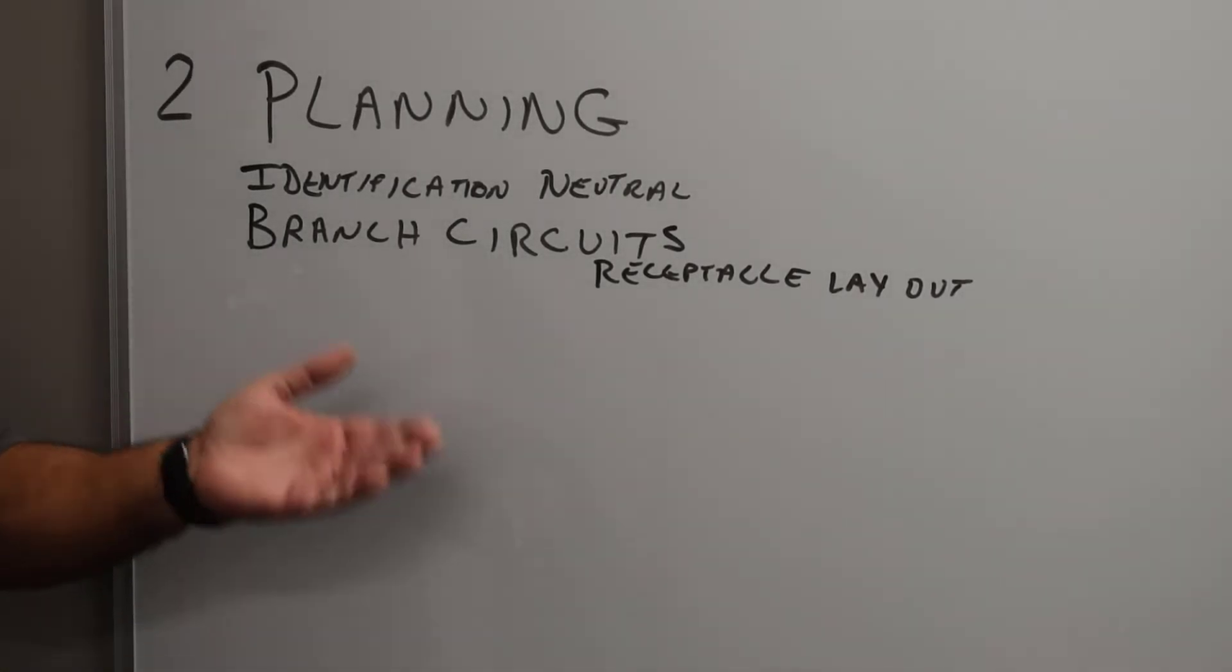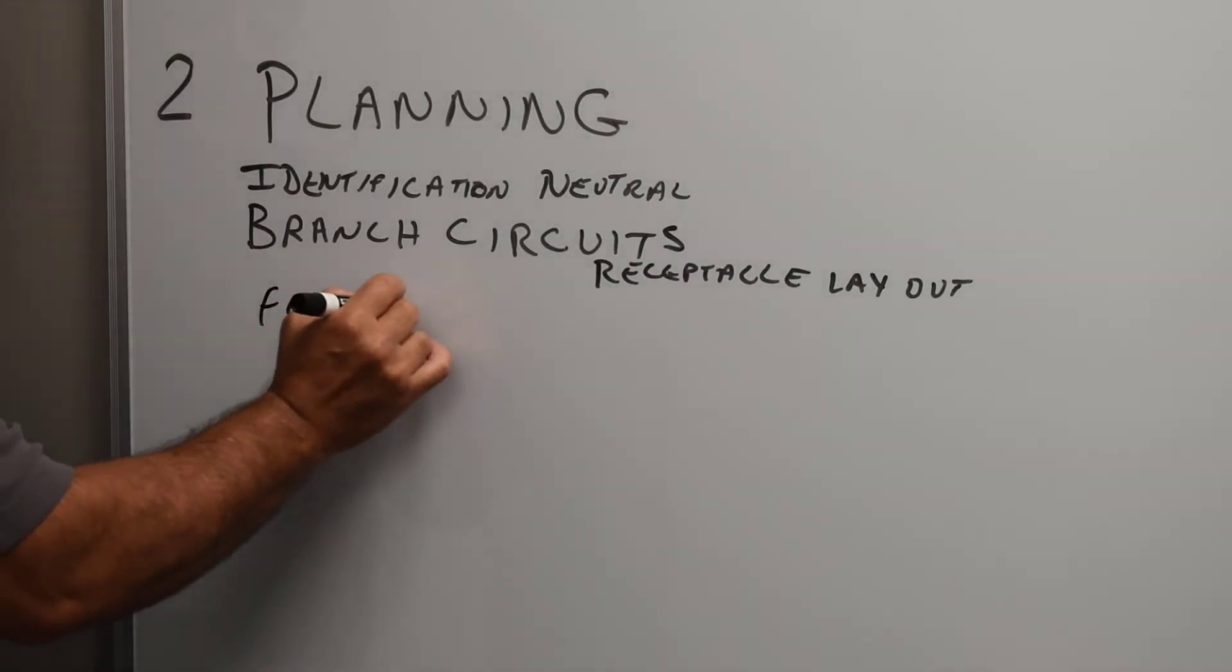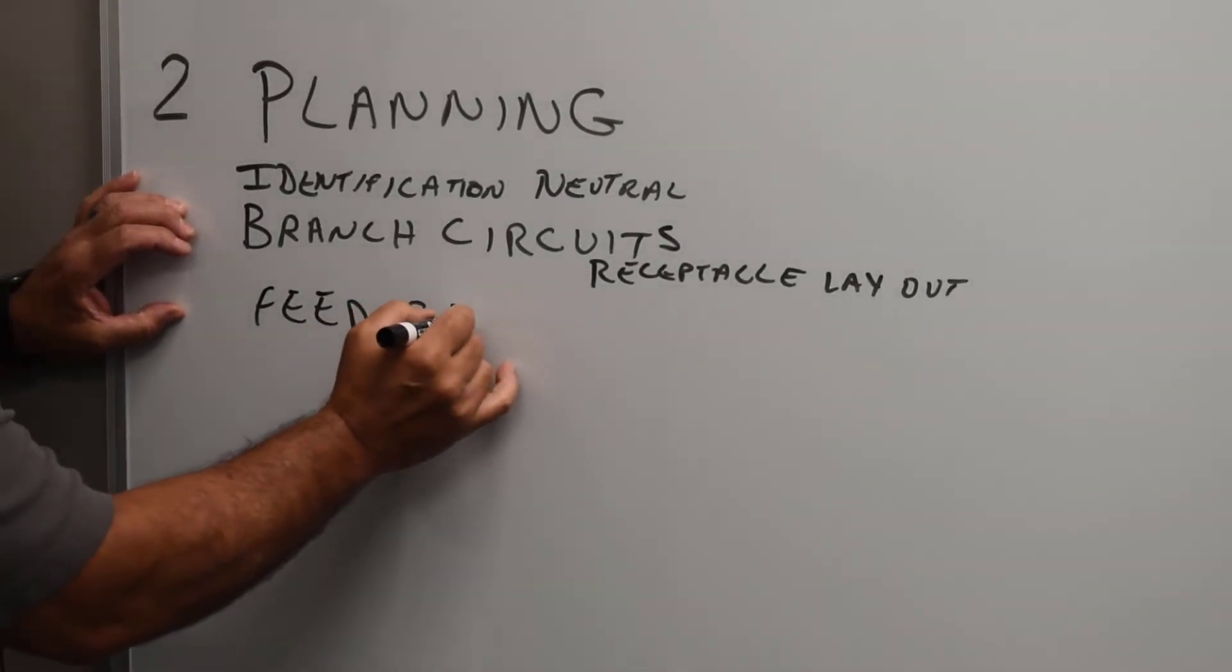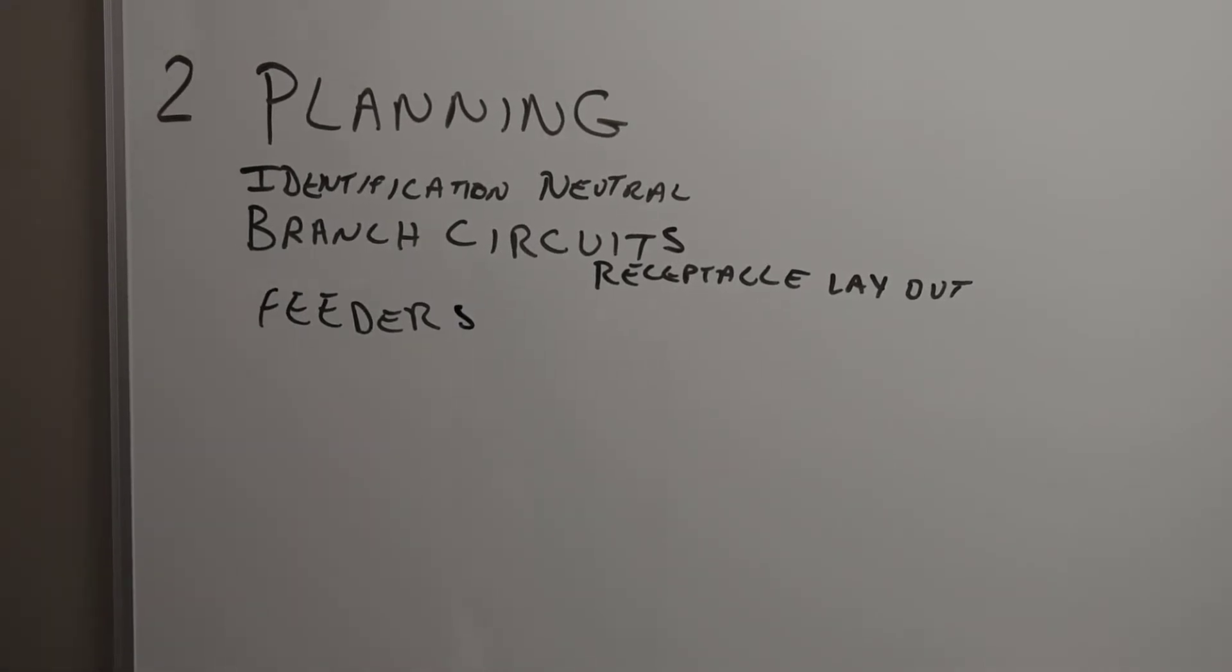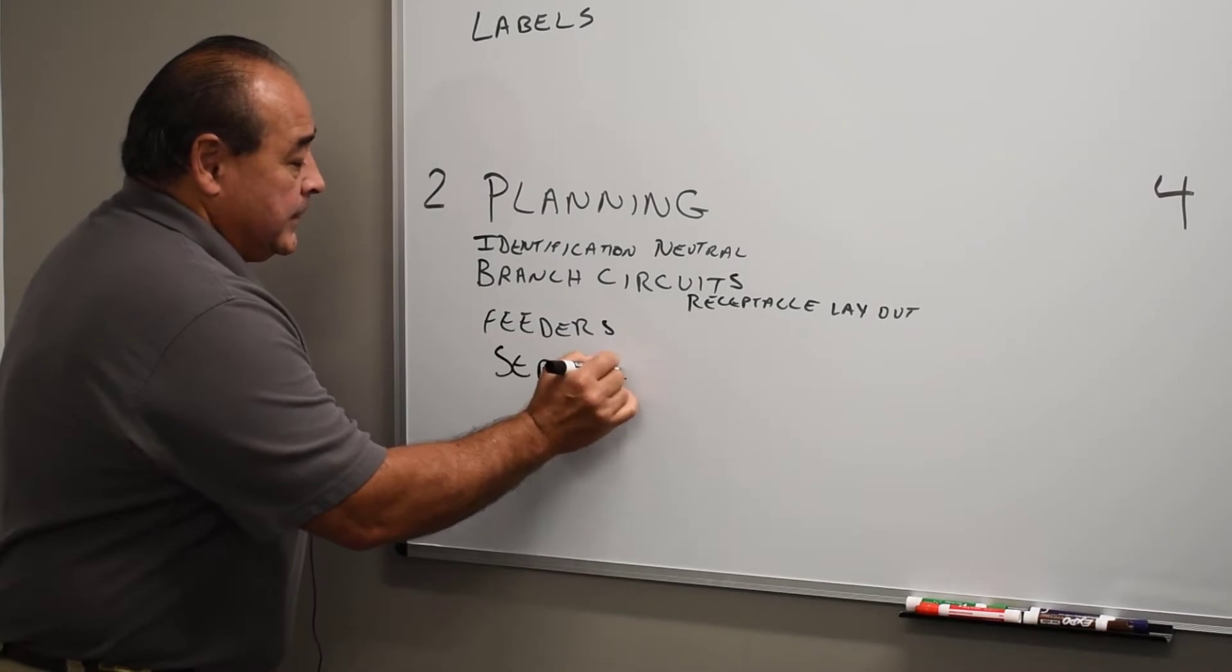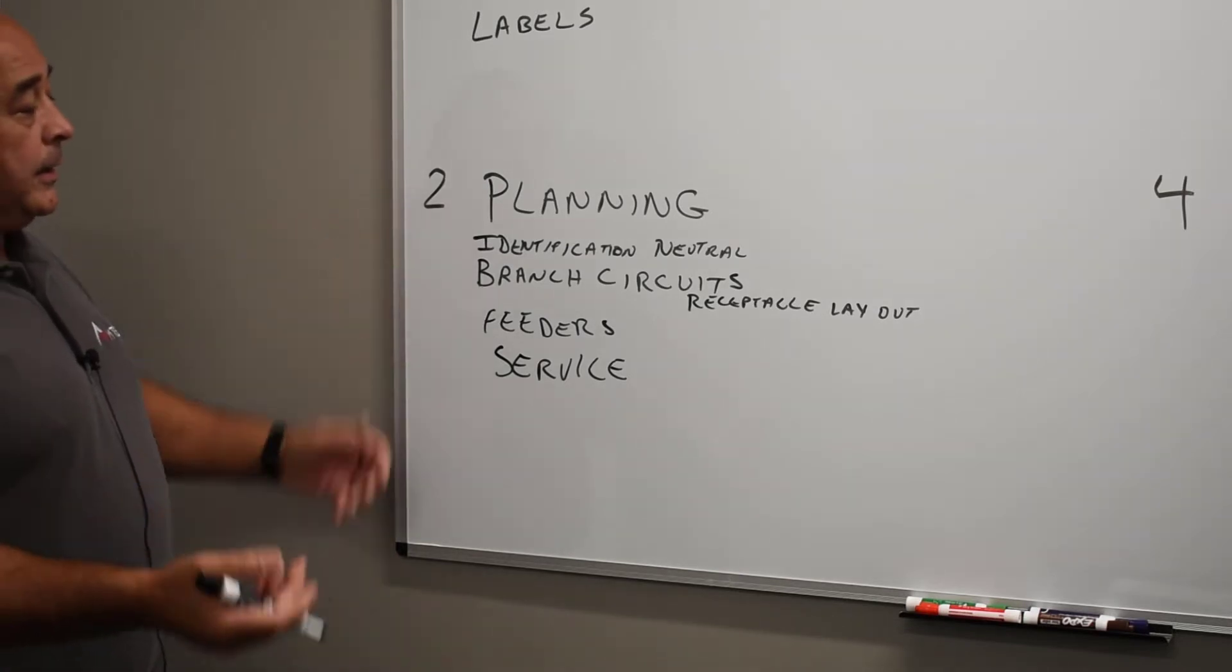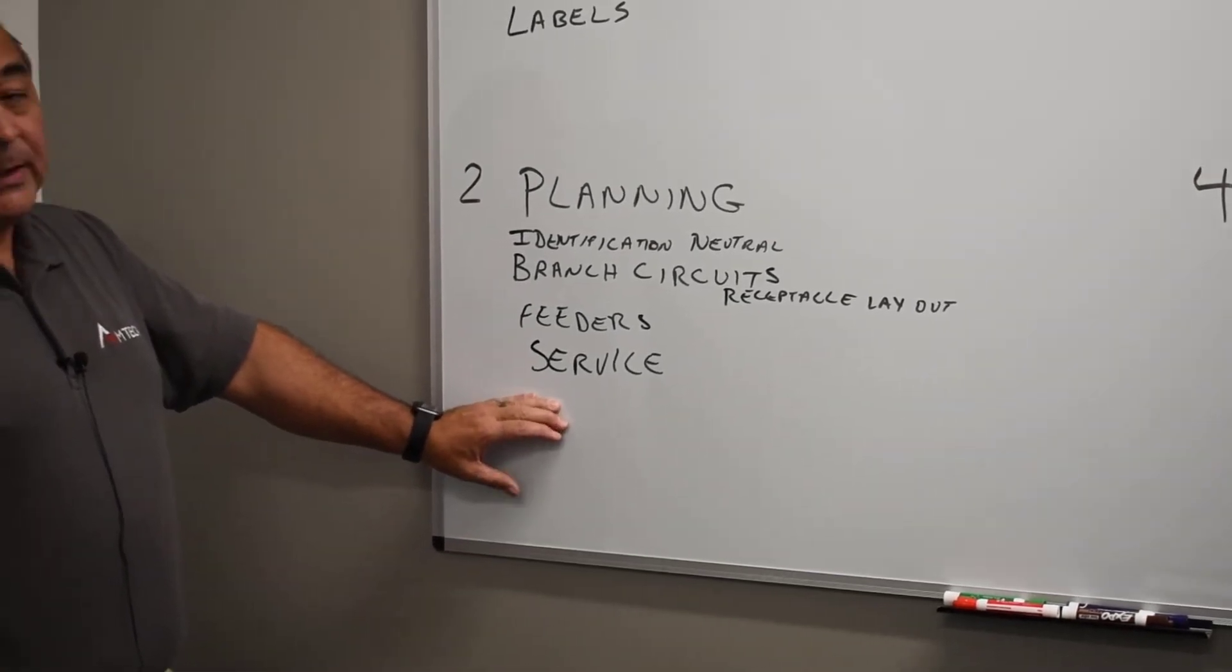Then we get into feeders. Well, feeders go to our distribution equipment and take care of the needs of the branch circuits. One leads into the other. And once we know how many feeders that are required for the branch circuits, we get into services. The services, that's how we size the total load to take care of feeders, and feeders take care of the branch circuits, on and on, so just a cycle. Once we understand what size service we need, then we have to build a grounding electrode system.